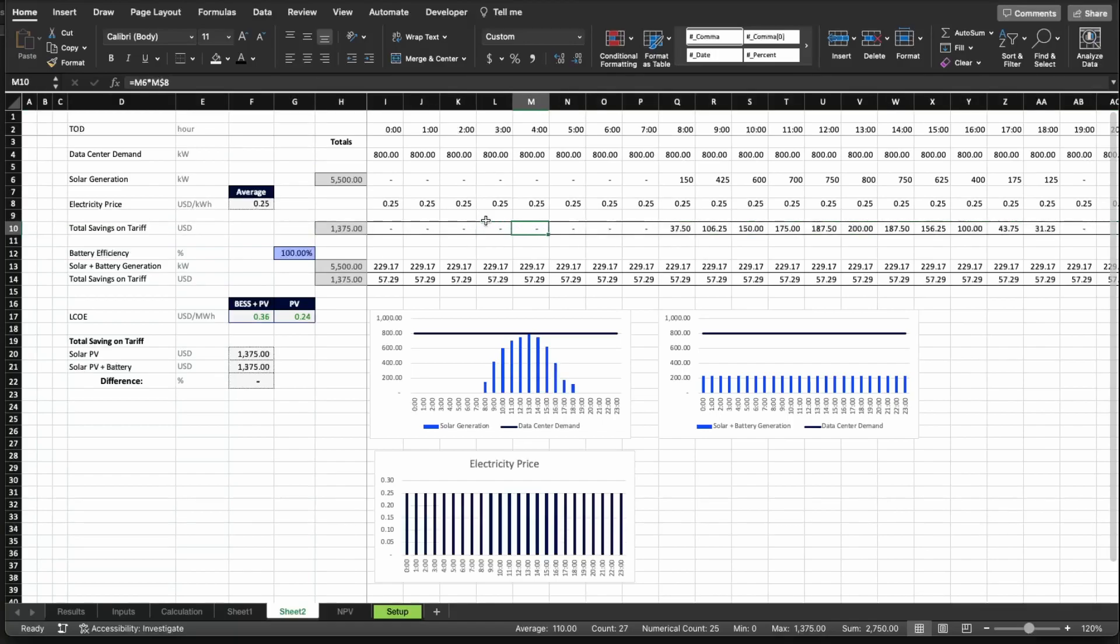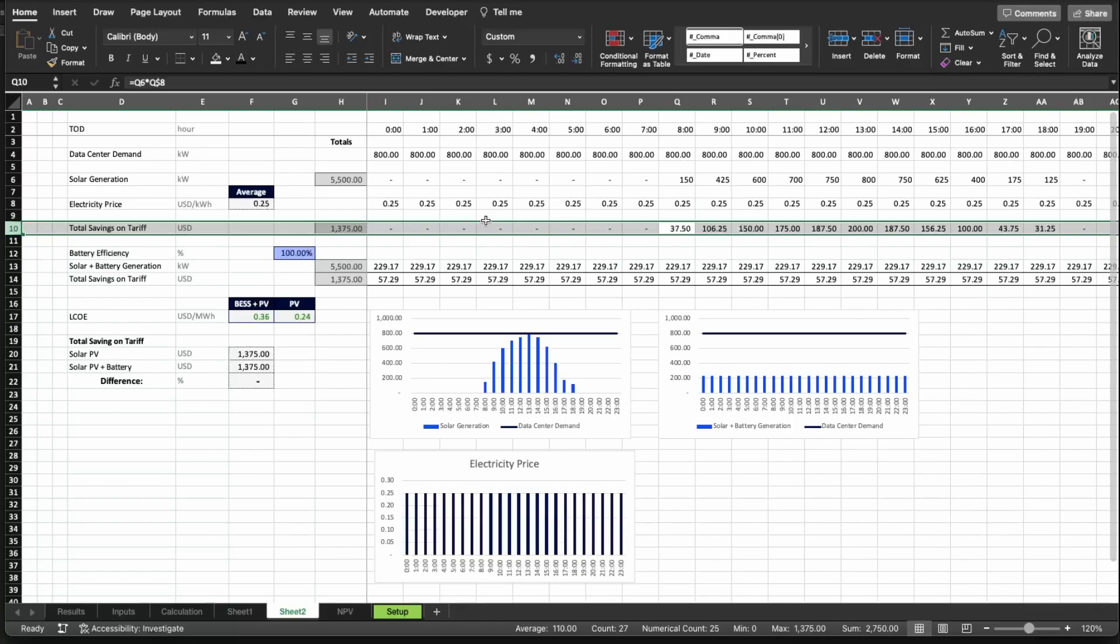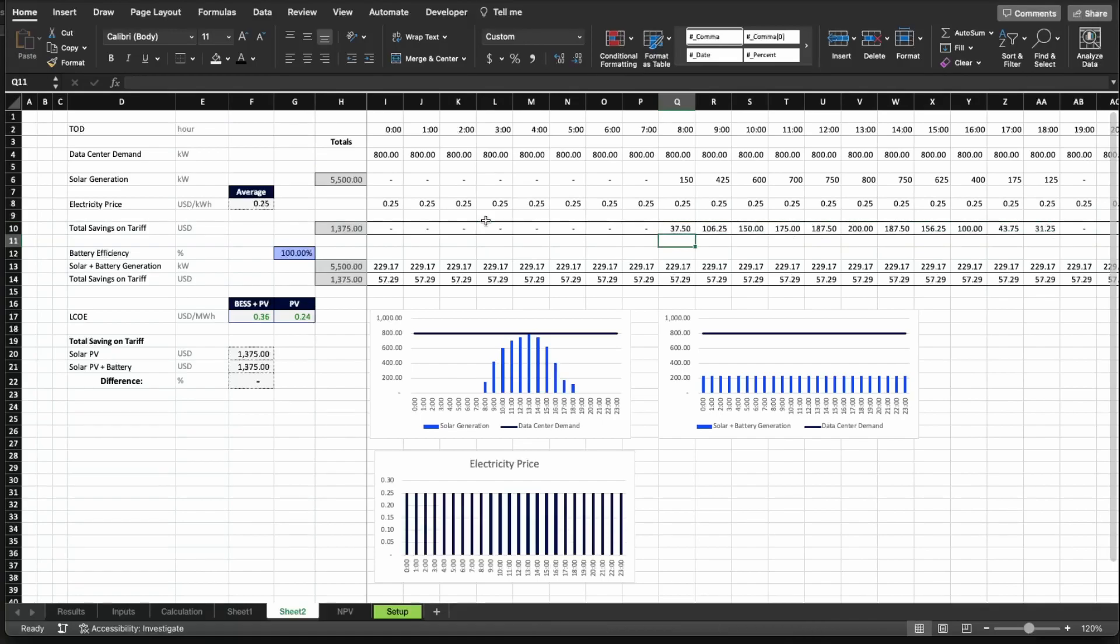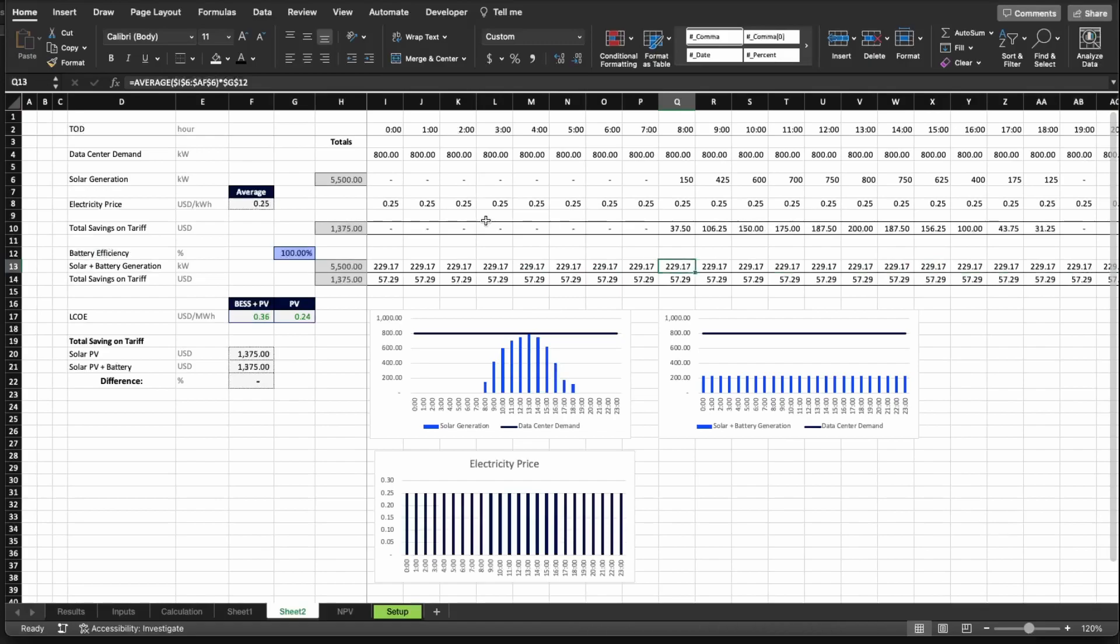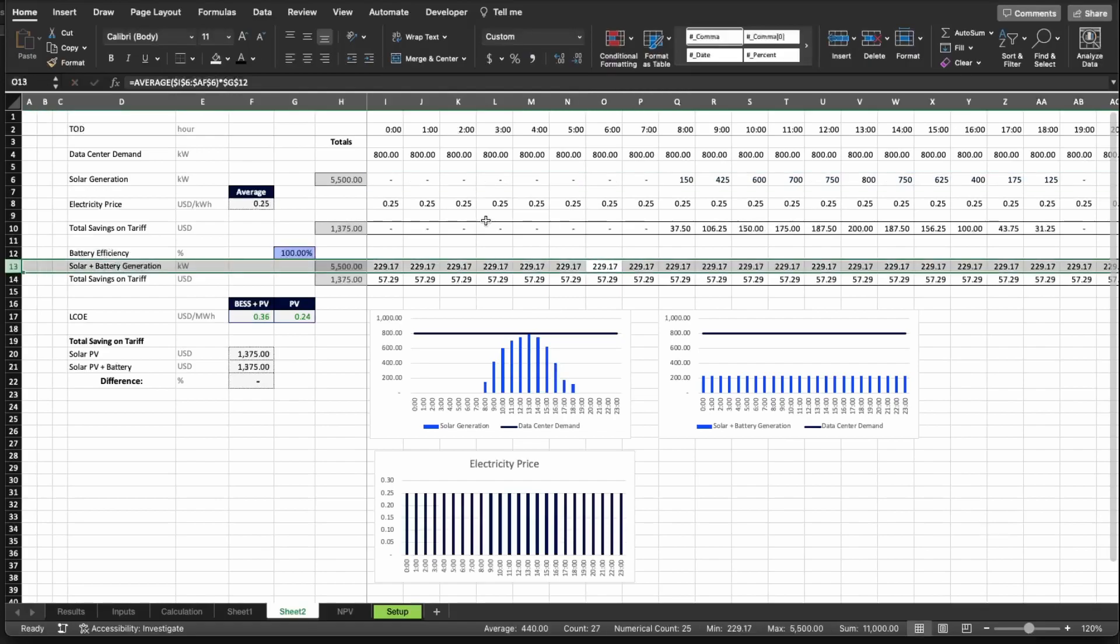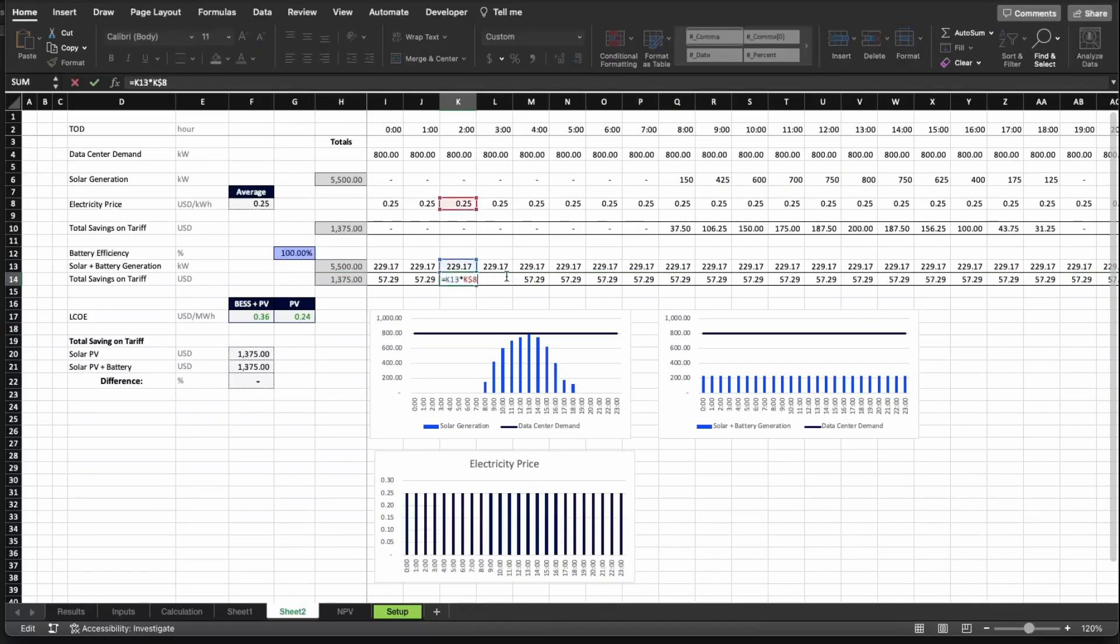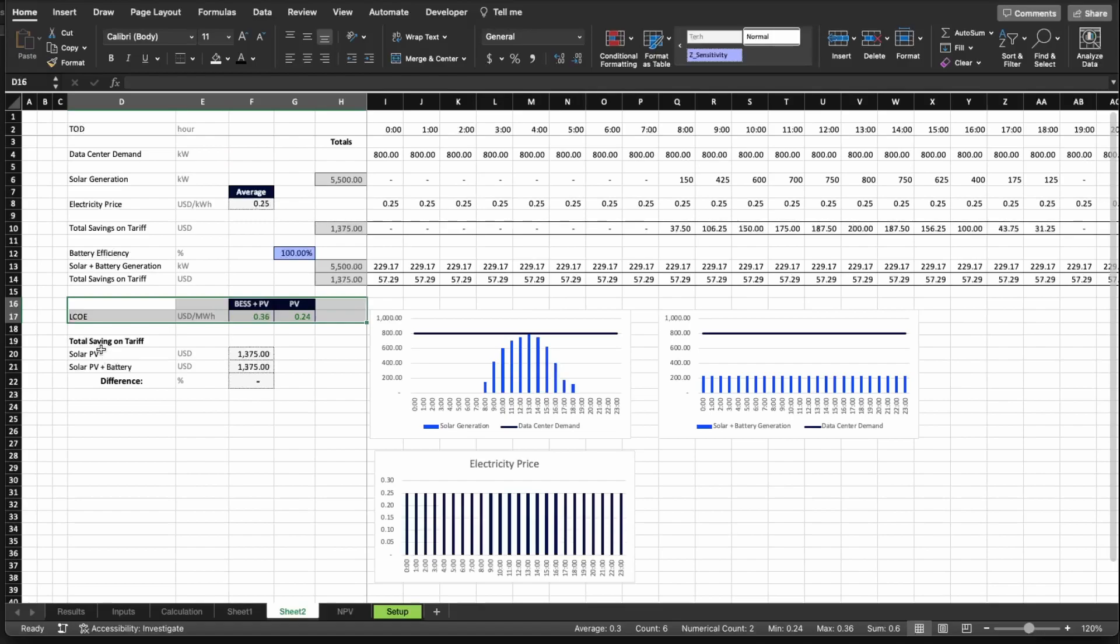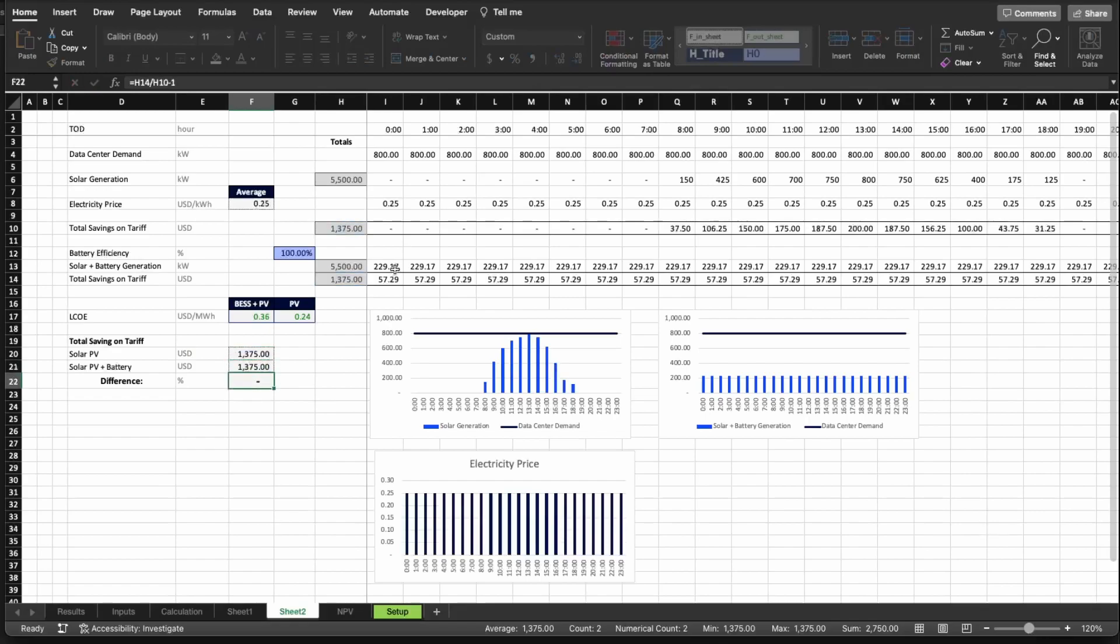And on row 10, we have what is the total savings on tariff if the client were to install the system, which is essentially the multiplication of how much generation the total system is giving to the client multiplied by the given price. We're going to save every day $1,375 to the client. Then we have the battery plus PV system with 100% efficiency, and I'm calculating a flat demand with total generation per day of 5500 kilowatt hours. And then I'm calculating the total savings for the tariff for this particular client, multiplying the price of electricity times the generation. And as you can see here, the total savings for both systems is the same. There is no difference. So this is scenario number one.